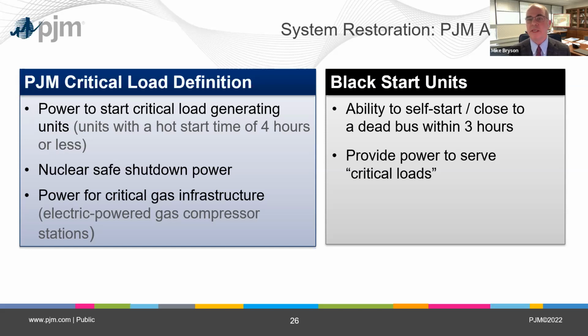We also use black start for nuclear safe shutdown power. And one of the critical things we do, based on the 2011 Southeastern blackout and reaffirmed last year, is making sure we have enough black start to get power for critical gas infrastructure up and running. Our black start units have to be able to self-start and close to a dead bus -- meaning no electricity coming in from the outside -- within 3 hours, and then provide that power to critical loads.